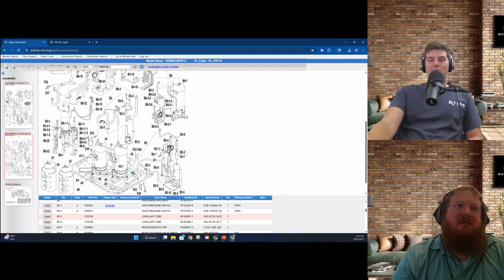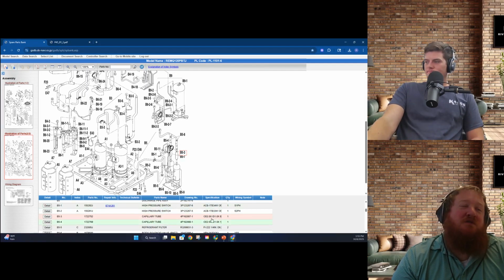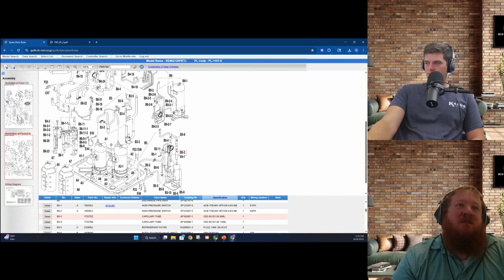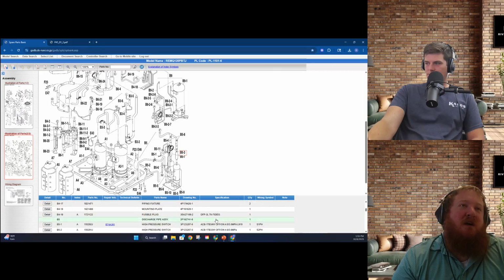So if you're changing cap tubes, and this is the second time you've changed a cap tube, the third time you've changed a cap tube, just change the daggum compressor. What are you waiting for? Yeah, I think we'd make it pretty common practice. If the cap tube is broken, first of all, go find your leak. Make sure that you have your refrigerant intact. Make sure your system's intact before you put new refrigerant in. And there's more than a 50% chance that compressor is probably bad.